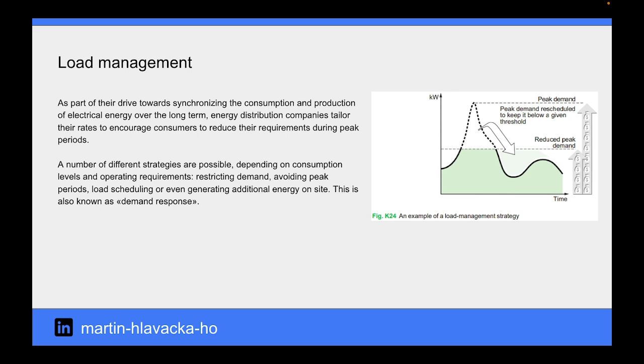What is demand restriction? Energy distribution companies can use this solution in supply contracts containing optional or emergency restrictive clauses whose application is determined by the consumer. This management policy is typically used during the hottest or coldest months of the year when companies and private customers have very high requirements for ventilation, air conditioning, and heating, and when electricity consumption exceeds normal demand considerably. Reducing consumption in this way can prove problematic in residential and service sector environments, as it may considerably inconvenience building occupants.